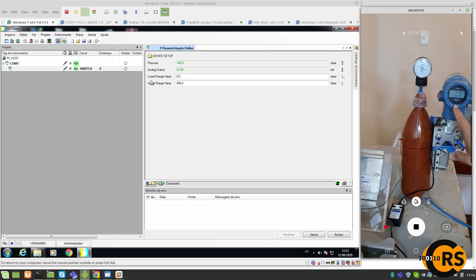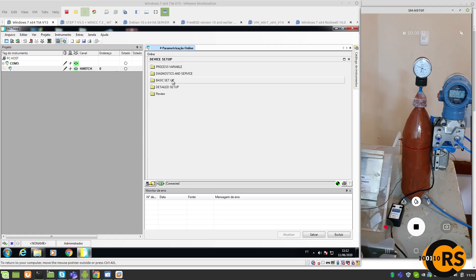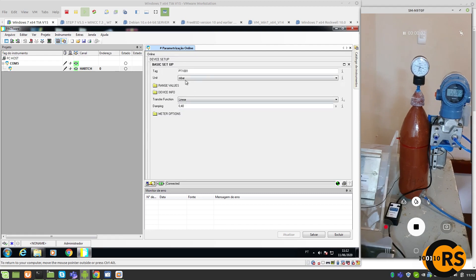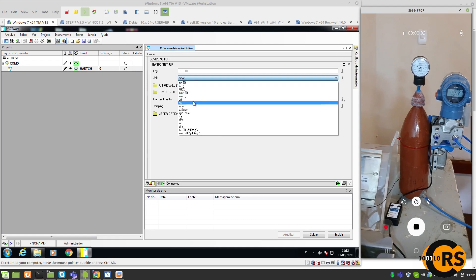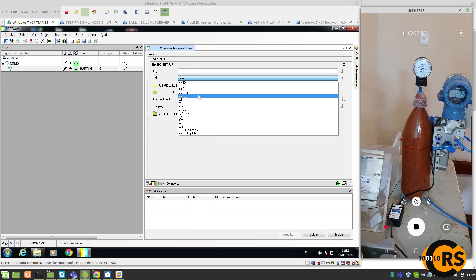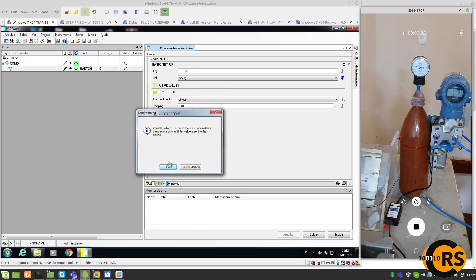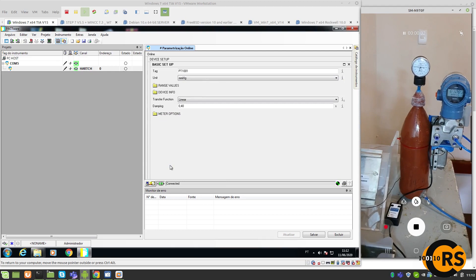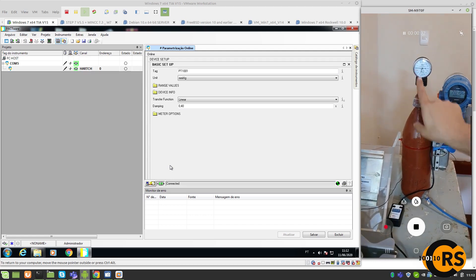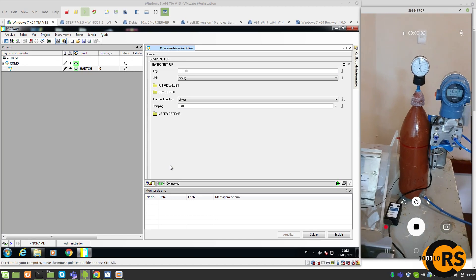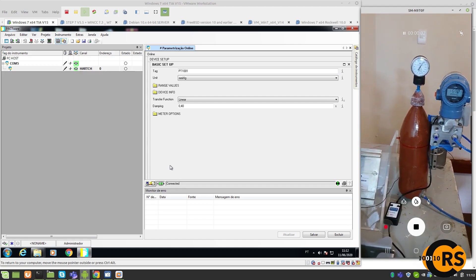We can now change some parameters. Notice that the manometer is different from the transmitter — the manometer scale is in millimeters of mercury while the transmitter is in millibar. I'm going to set the same scale in the transmitter. I can go to Device Setup, Basic Setup, and change the unit now to millimeters of mercury. Look — now it shows millimeters of mercury. Around 60, 80 — it's checked. Decreasing now, now it's increasing. 160, 160 — I'm going to get to 300 millimeters of mercury.